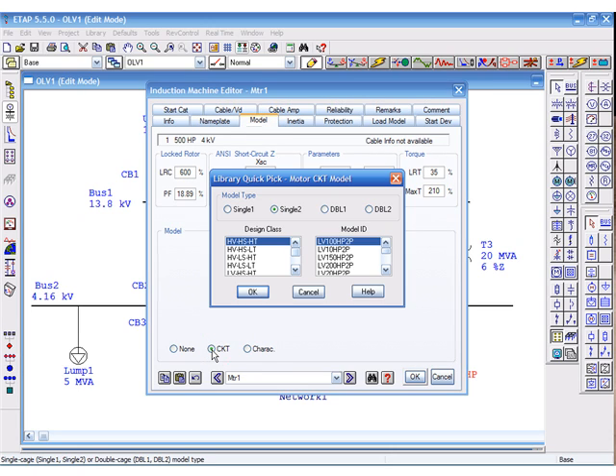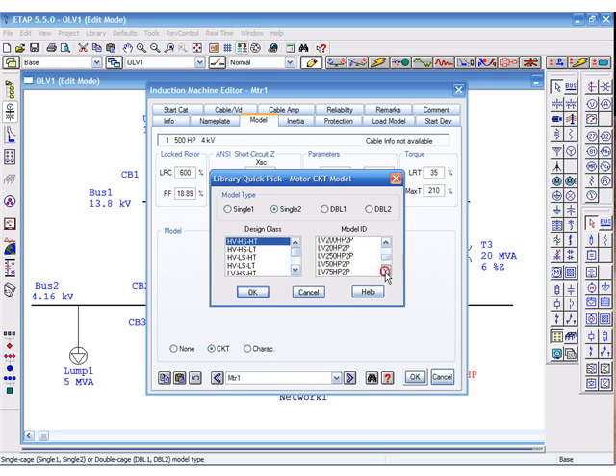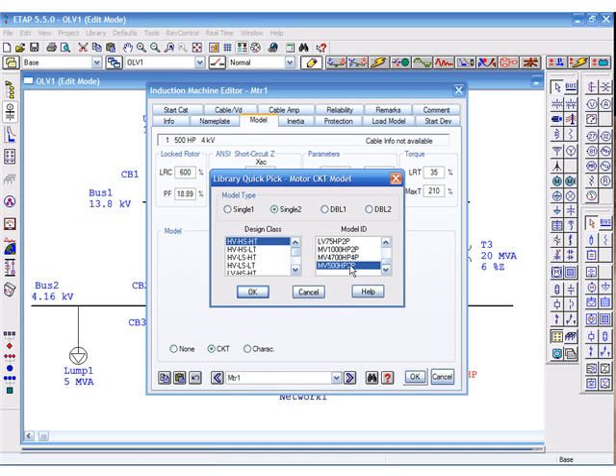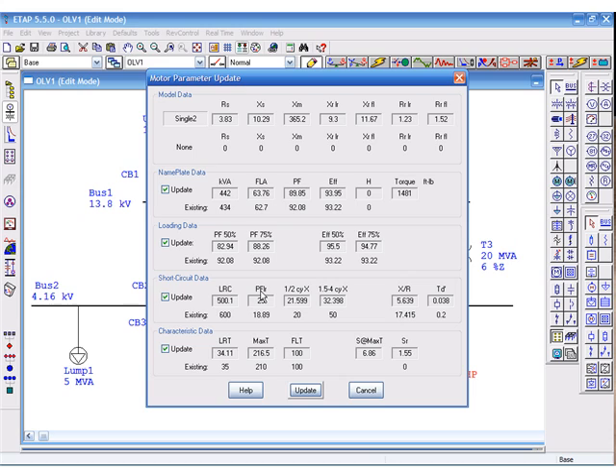We'll start off with the model page, where you can select the circuit model of this motor from the library. Note that this model should be entered in for the motor you're trying to accelerate. The data in the library is sample data for a specific 500 horsepower motor. The circuit model information includes the rotor and stator impedance values.